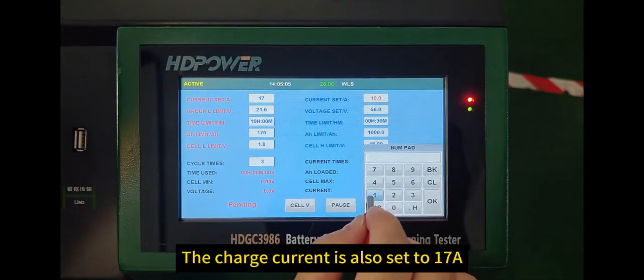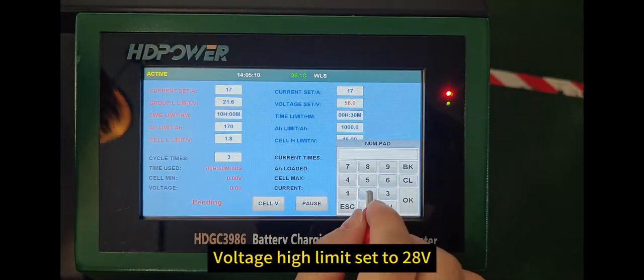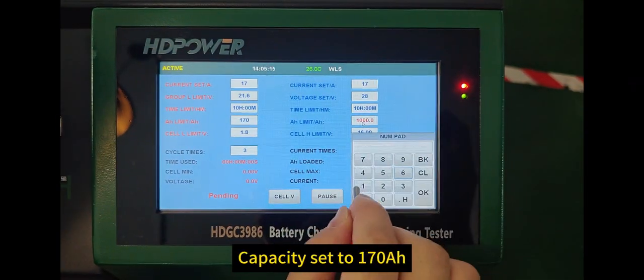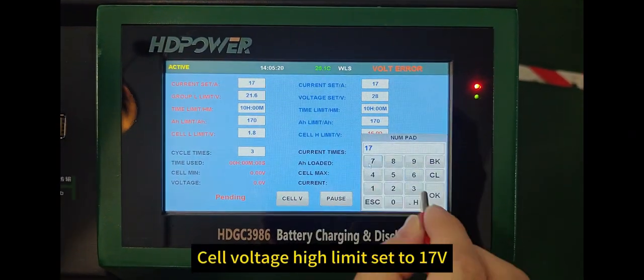The charge current is also set to 17A. Voltage high limit set to 28 volts. Test time limit set to 10 hours. Capacity set to 170 Ah. Cell voltage high limit set to 17 volts.